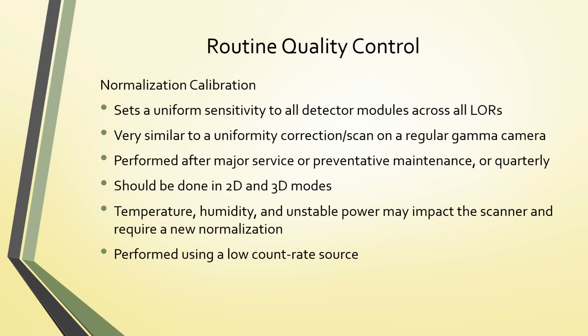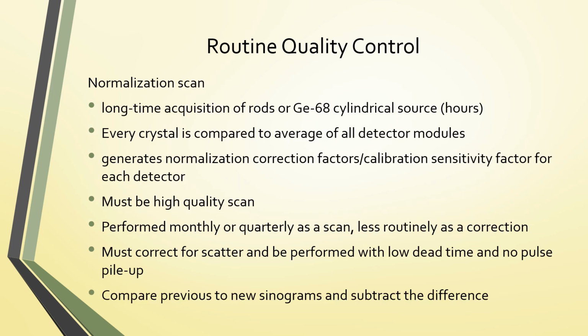And this is performed using a low count rate source. A normalization scan is a long-time acquisition of the rods or germanium-68 cylindrical source. This takes several hours to complete. A lot of times technologists will set it at the end of the day and it will perform overnight. Every crystal is compared to the average of all detector modules, and it generates the normalization correction factors, the calibration sensitivity factor for each detector. It has to be a high quality scan, and that's one of the reasons that the acquisition takes hours. It's gathering a lot of counts.